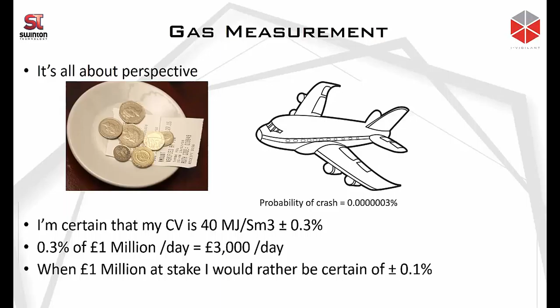So we talk about 0.1% uncertainty of the GC because a GC is actually capable of performing around 0.1%, 0.12% in most of the GCs that I've seen so far. But a lot of times people actually put in their uncertainty budget of a CV measurement of 0.3%. And that's actually a lot higher uncertainty expectation than the GC is actually capable of.